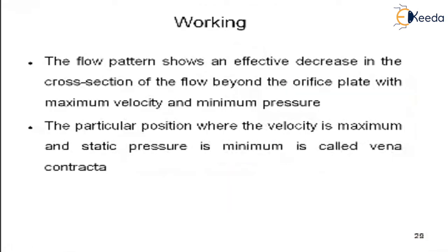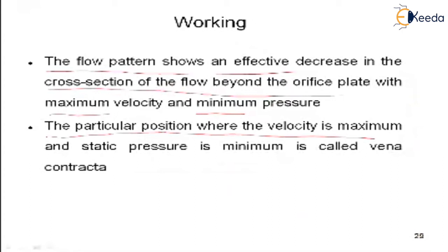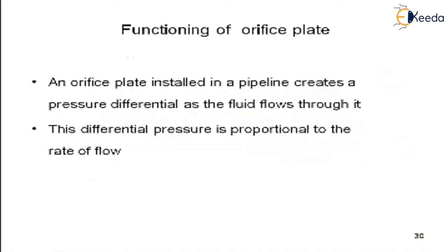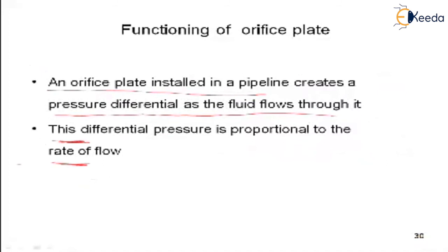The flow pattern shows a decrease in the cross-section of flow beyond the orifice plate, with maximum velocity and minimum pressure. The position where flow velocity is maximum and static pressure is minimum is called the vena contracta. This orifice plate, installed in the pipe, creates a pressure differential as fluid flows through it, and that differential pressure is proportional to the rate of flow.